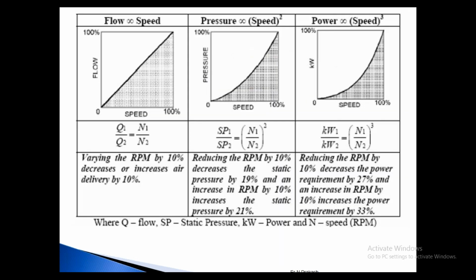So you have to see the fan chart and run the fan at a particular speed to achieve the required or recommended power. It should not increase, it should not decrease. Again, you increase the flow, decrease the flow. As I mentioned, changing the flow will change the pressure also. If you are reducing the speed of the fan, it is going to reduce the flow. So there could be a reduction in the flow.